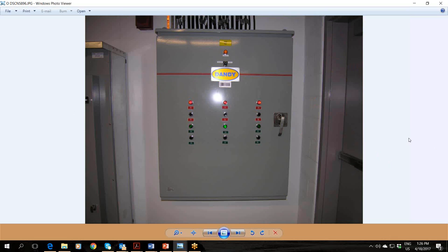This is a picture of the control cabinet for the 600 volt switchgear. As the utility, our demarcation point into the buildings is a little bit different. We basically control the main tie main for the low voltage switchgear lineup, and then the buildings group takes over past that. And that's true for both internal to U of A as well as external customers, at least in terms of operation. In terms of ownership, it's pretty much at the building wall. The building, when it is built, has to pay for all the stuff inside the building, including the medium voltage switchgear that we operate. So the demarcation for ownership is different than the demarcation for operation. It's a little bit different as well.